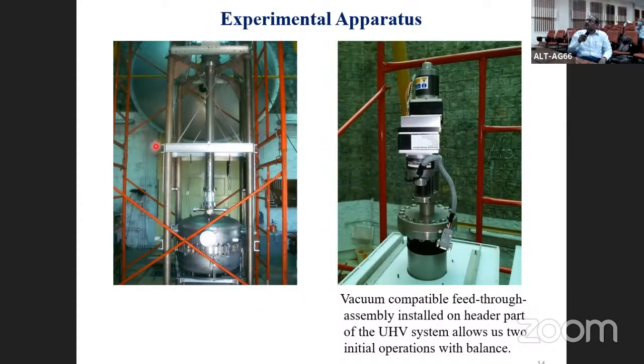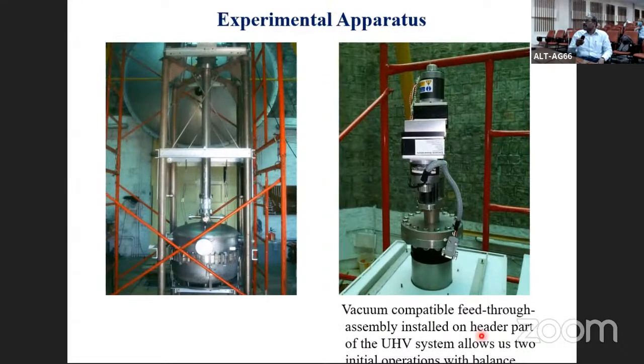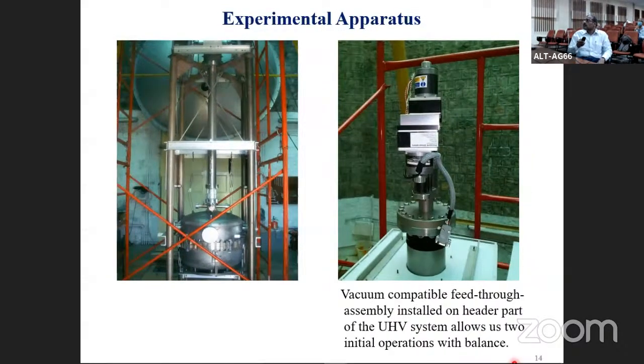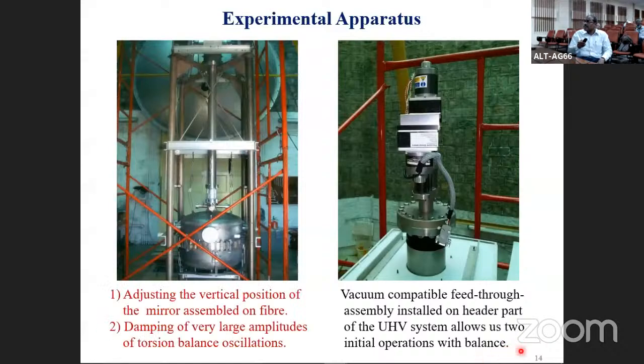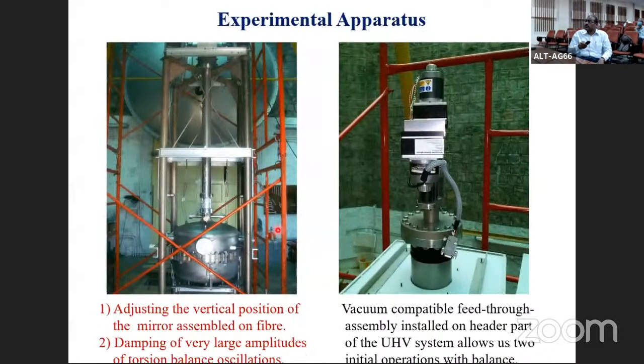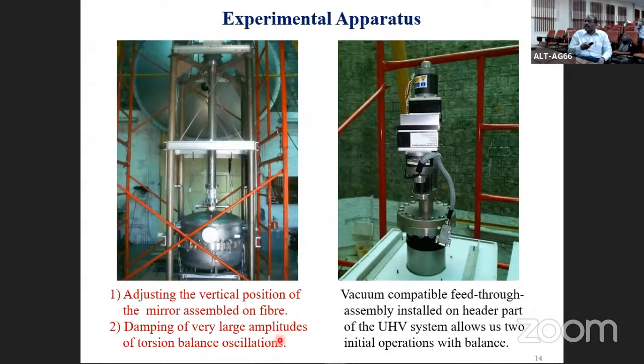On the top of the UHV header pipe, we have a vacuum-compatible feedthrough assembly, which allows us the initial operation with the balance. These are in direct contact with the balance, and these are used for coarse adjustment. These adjustments are for adjusting the vertical position of the mirror assembled on the fiber and for damping very large amplitudes of torsion balance oscillation.